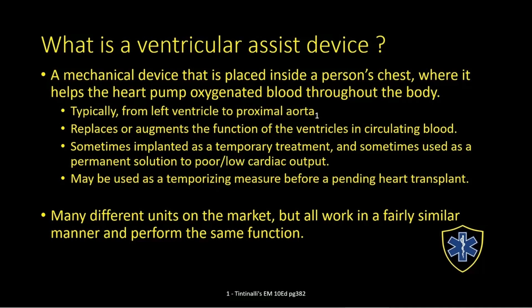Now, as we look at the typical parts of a ventricular assist device, typically there's going to be some type of battery pack, more than likely more than one of them, and there'll possibly be either a charger or a power supply. Now, this charger or power supply a lot of times will be plugged into the wall to a standard AC outlet. It may have a charger where you can charge 2, 3, or 4 batteries in the unit itself, and it may have a power lead coming from that going directly into the controller.